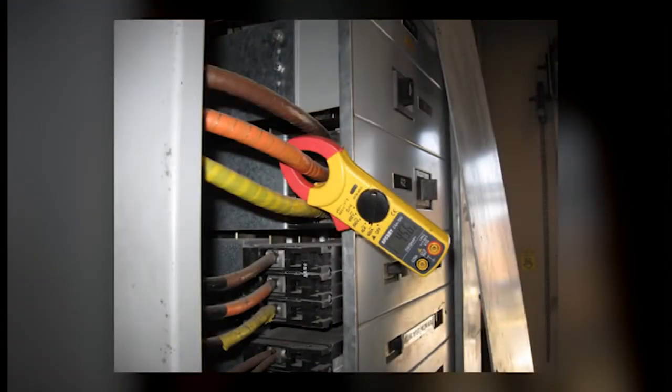We use a lot of clamp meters too. I know that clamp meters don't give you true power. We use true power monitoring equipment where it's important to get power factor and a really accurate measurement. A lot of amp readings are better than no true power readings. So go back and get the true power later. Some data is better than none.